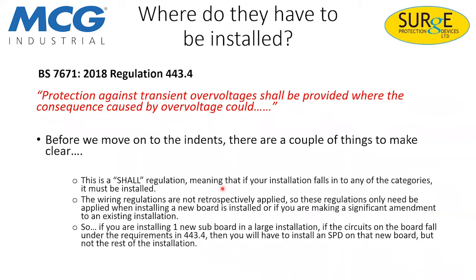So we'll start having a look at the 18th edition regulations. 443.4, protection against transient overvoltages shall be provided where the consequences caused by overvoltage could. Before we move on to the indents, there are a couple of things we need to look at. This is a shall regulation, meaning that if your installation falls into any of the categories, it must be installed. You can't say your client doesn't want it or decide it costs too much money. It needs to be done.